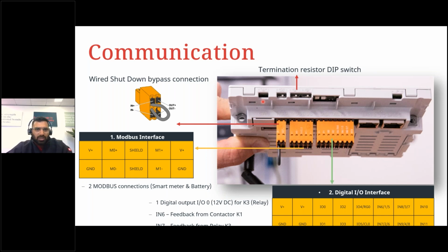So another topic here is that we have these terminating resistors already as a dip switch. By default, they are both on. So depending on your needs, you might sometimes have to turn it off, depending on where the inverter sits in the chain in the Modbus line. So if it is not the end of the line, you might have to turn these resistors off.